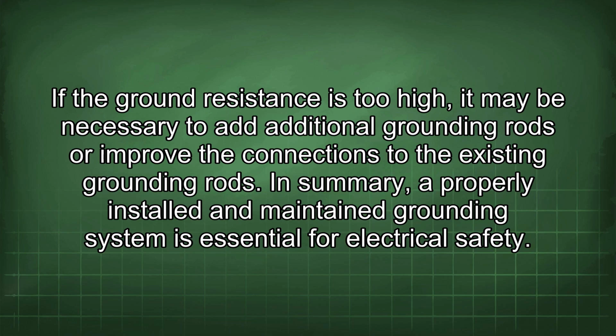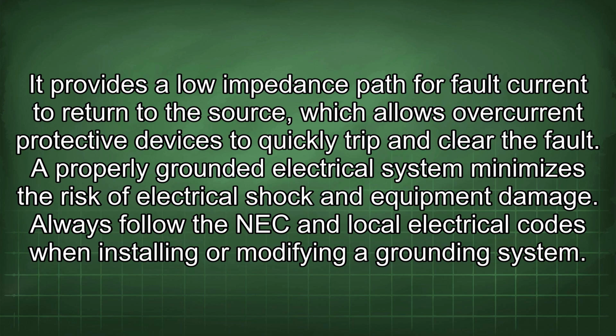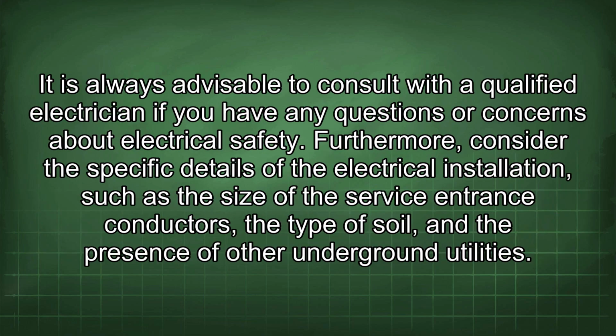In summary, a properly installed and maintained grounding system is essential for electrical safety. It provides a low impedance path for fault current to return to the source, which allows overcurrent protective devices to quickly trip and clear the fault. A properly grounded electrical system minimizes the risk of electrical shock and equipment damage. Always follow the NEC and local electrical codes when installing or modifying a grounding system. It is always advisable to consult with a qualified electrician if you have any questions or concerns about electrical safety.